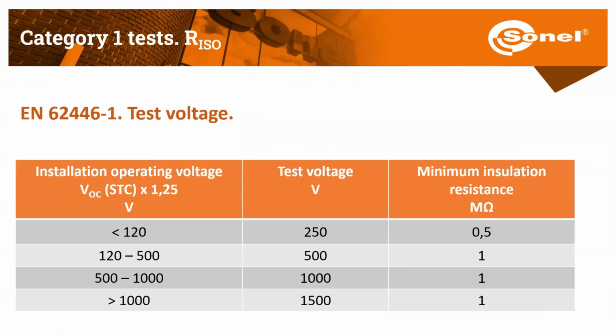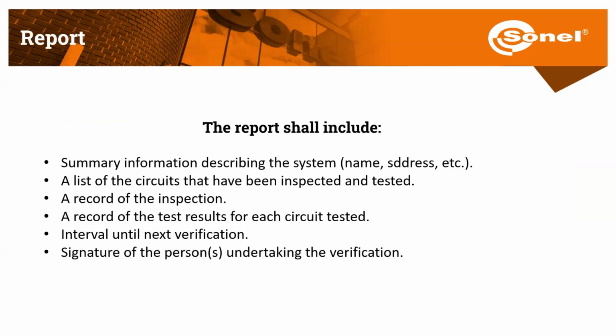The standard describes minimum insulation resistance values, but in practice, the values we usually see are much higher than required. You see the standard, we have 1 mega ohm. Normally, we have even 1 giga ohm of resistance. The post-inspection report should include system information and a description of the visual inspection and any deviation measurement values, and it should be signed by a qualified person, of course.